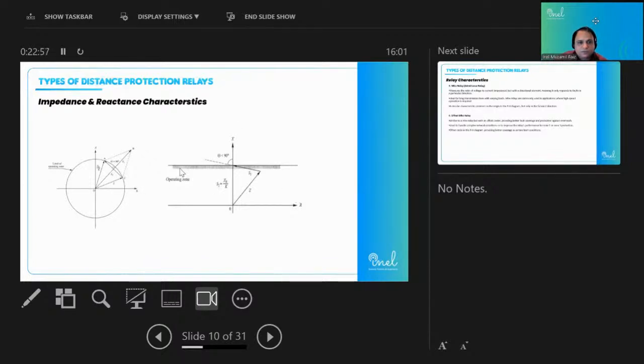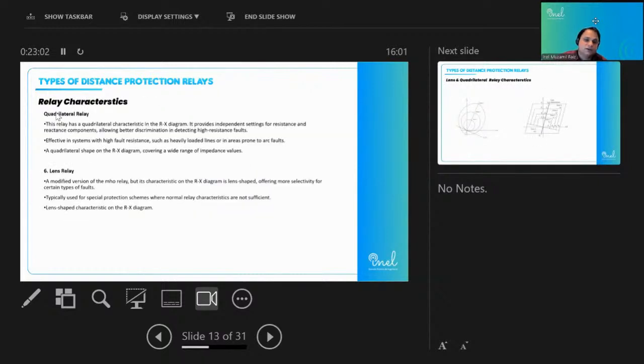To overcome this issue, there is a characteristic called the quadrilateral relay characteristic, and this is basically used on heavily loaded lines, and also on lines where the source connected to that transmission line is weak in nature. What we mean by weak in nature is that if the fault current at a location is less than a prescribed value, then we consider it a weak source. As we have discussed, this is also effective when there is fault resistance, when the lines are heavily loaded, and also when there is an area which has a high arc fault ratio.